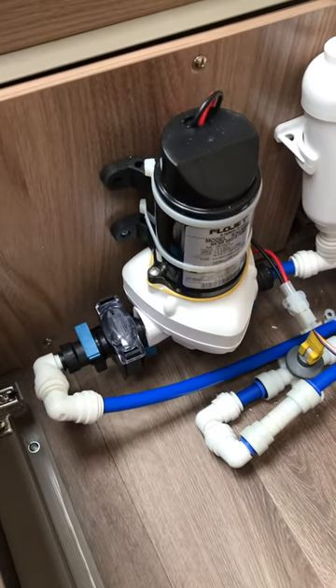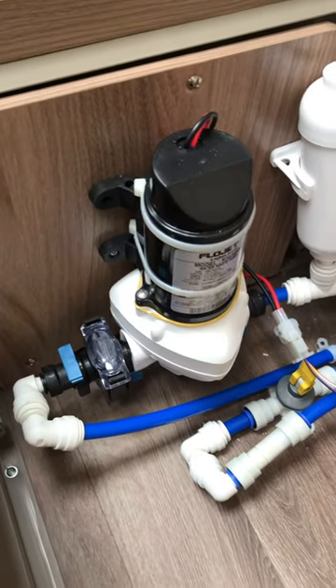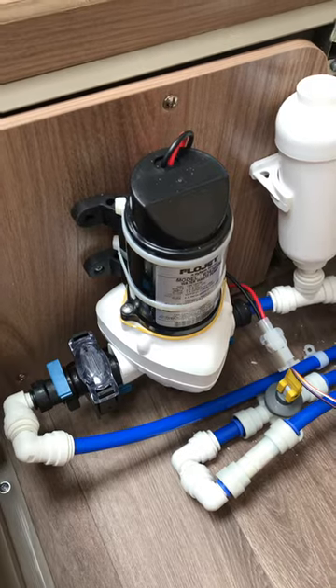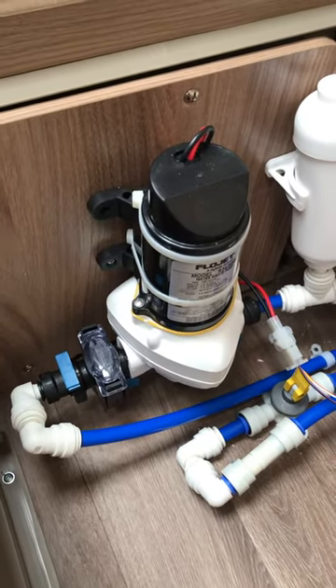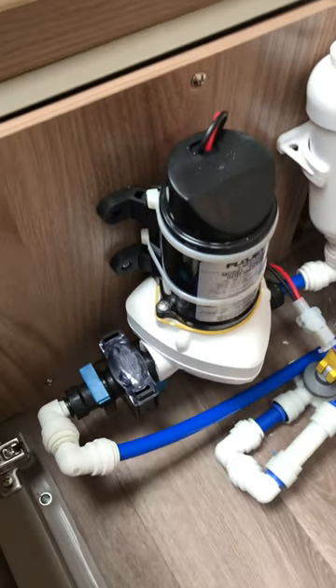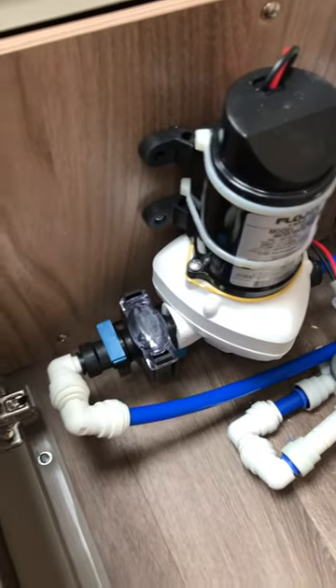This is just a quick video to explain how to remove the filter from a Flojet pump. Sometimes you'll get the Flojet not pressurizing up and you'll get coughing and spluttering out the tap. It can sometimes be the filter split, and to test that you can remove the filter just to see if it resolves the problem or not.